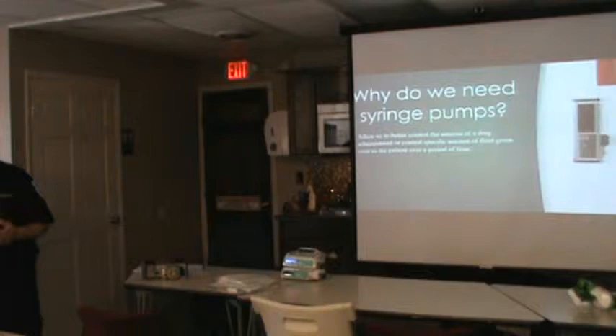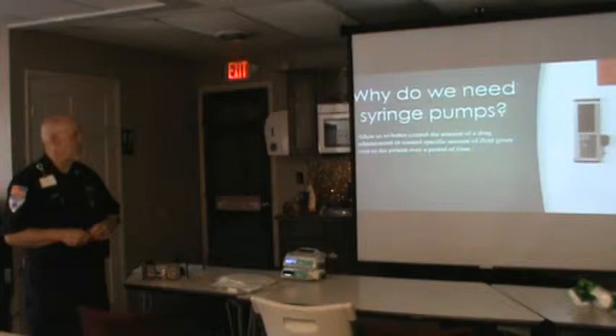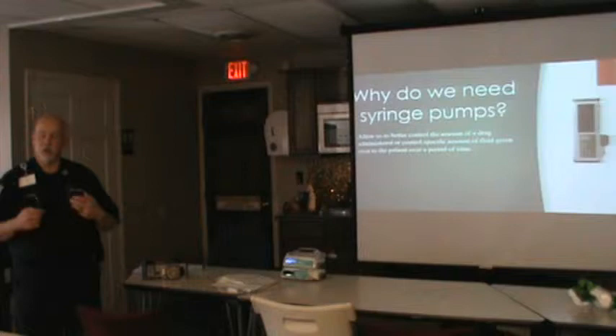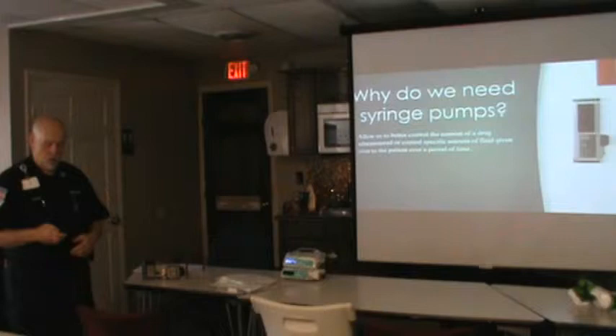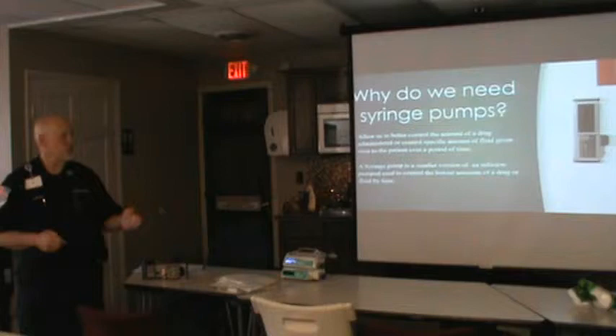Syringe pumps — back in the day we used Dial-A-Flow to control everything. A syringe pump lets us control the amount of medication or fluid given over a specific period of time, so it gives us much better control over what we're giving. You can give a small bolus, you can purge the line — you can do everything with this syringe pump.